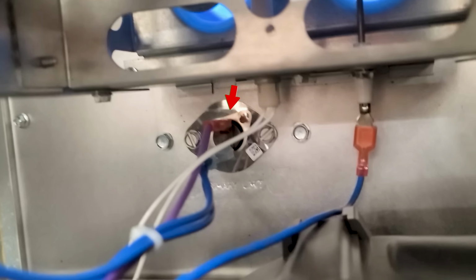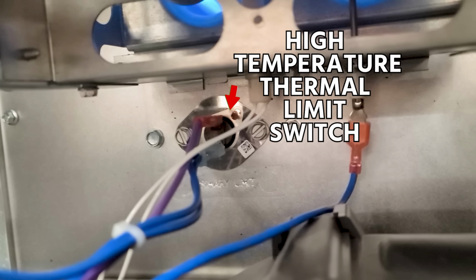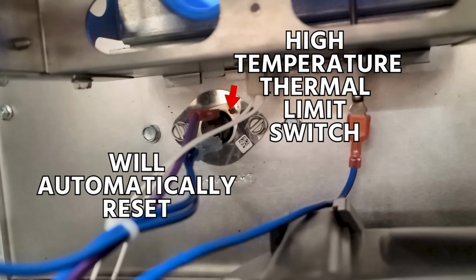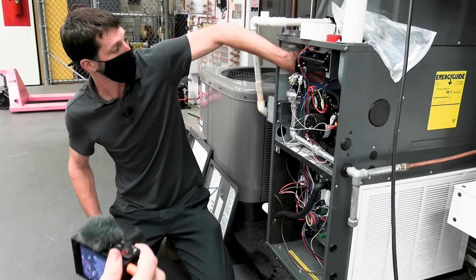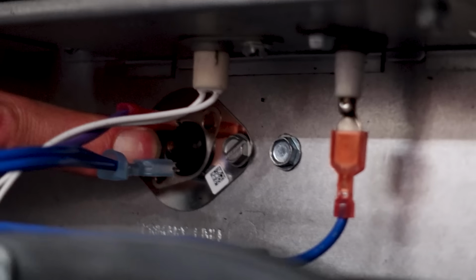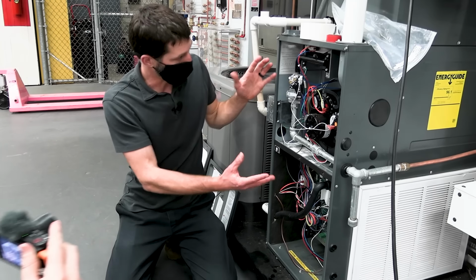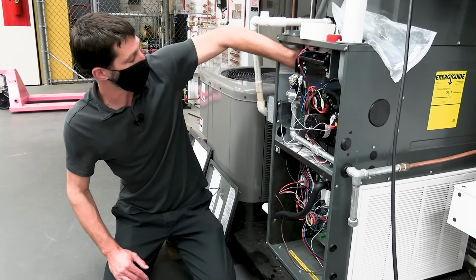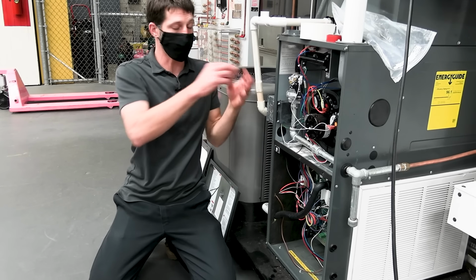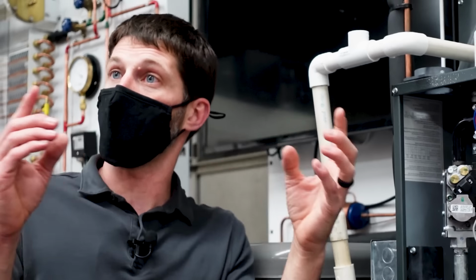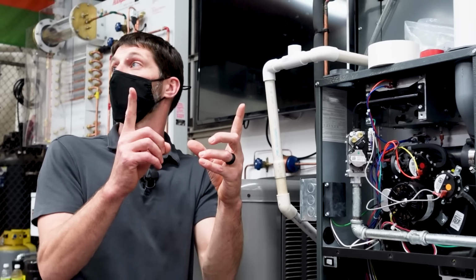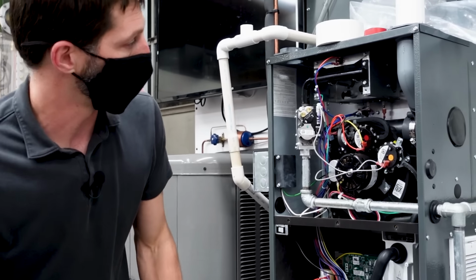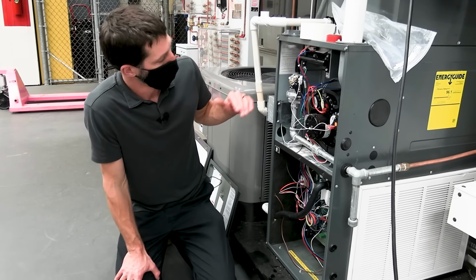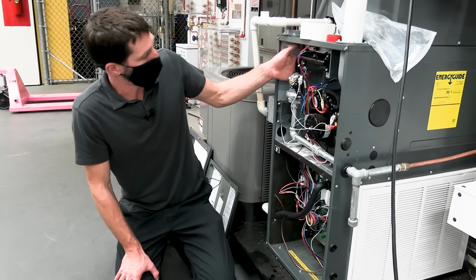So this right here is a high temperature thermal limit switch, and this will automatically reset, and this temperature is taken right in the heat exchanger area. And there's different versions of this depending on the model of furnace. This particular one looks like it just has the bimetal disc right at the opening. There are other ones that extend into the heat exchanger area, say that far or that far in there. There's also a fan control limit switch as well. But anyway, that's the norm right there.